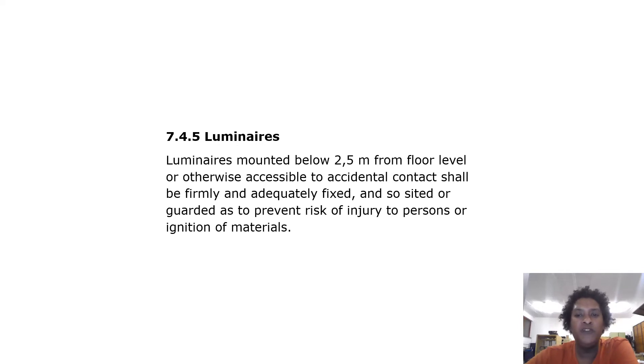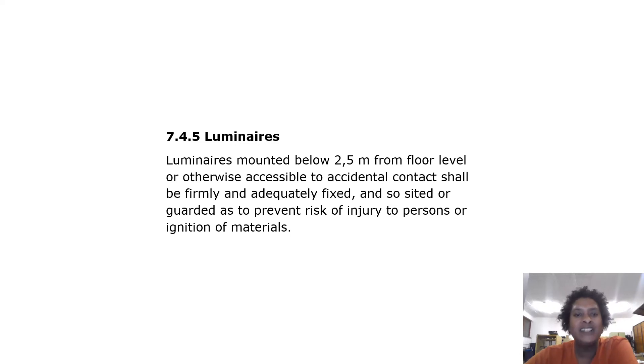Luminaires mounted below 2.5 meters from floor level or otherwise accessible to accidental contact shall be firmly and adequately fixed, and so sited or guarded as to prevent risk of injury to persons or ignition of materials.